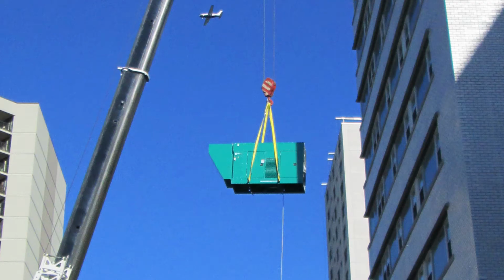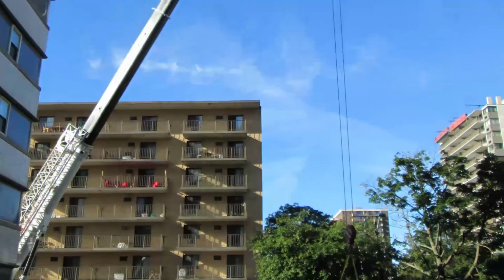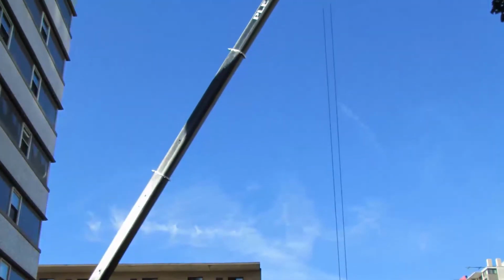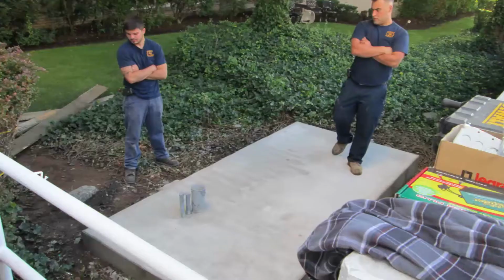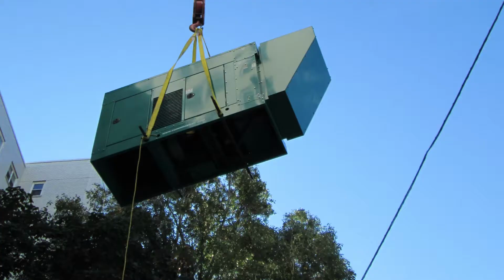We're craning the genset into place. Because of the layout of the property, we had to bring in a rather large crane. That's a 140 ton rated crane to make the pick because of the distance from the crane to where the genset pad was going to be. So we had to crane it up and over the building, over a section of the building and a section of the parking deck. We couldn't put the crane up on the deck because the deck wouldn't support the weight of the crane.